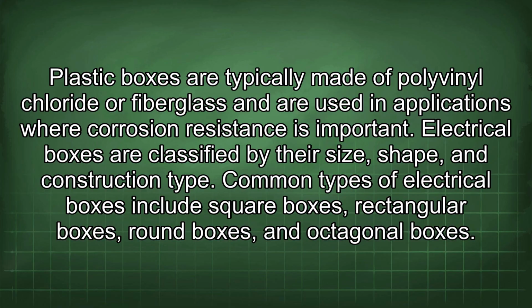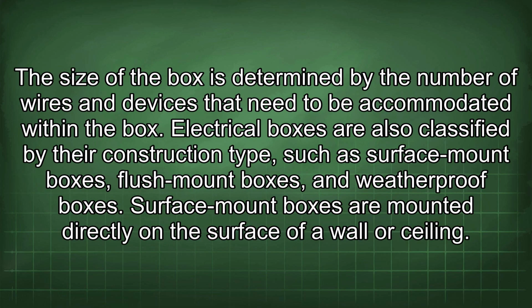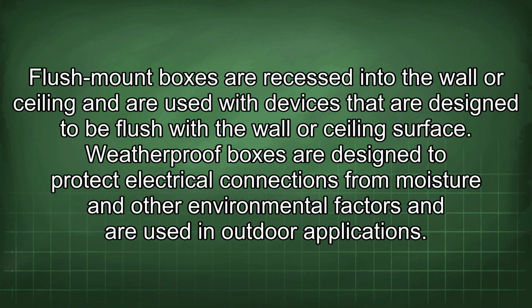Electrical boxes are classified by their size, shape, and construction type. Common types of electrical boxes include square boxes, rectangular boxes, round boxes, and octagonal boxes. The size of the box is determined by the number of wires and devices that need to be accommodated within the box. Electrical boxes are also classified by their construction type, such as surface mount boxes, flush mount boxes, and weatherproof boxes. Surface mount boxes are mounted directly on the surface of a wall or ceiling. Flush mount boxes are recessed into the wall or ceiling and are used with devices that are designed to be flush with the wall or ceiling surface. Weatherproof boxes are designed to protect electrical connections from moisture and other environmental factors and are used in outdoor applications.